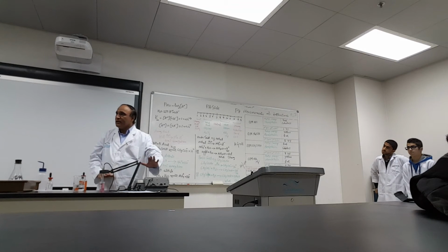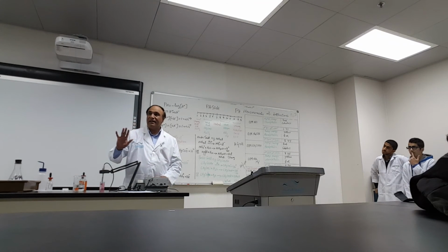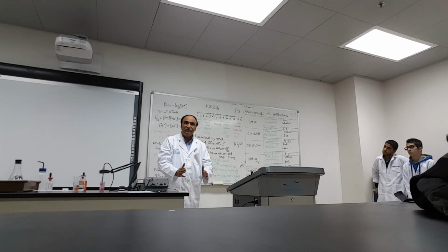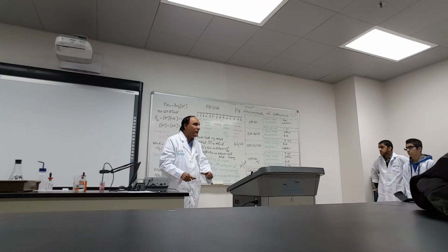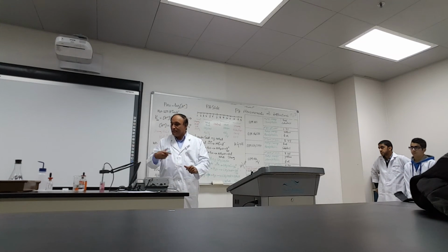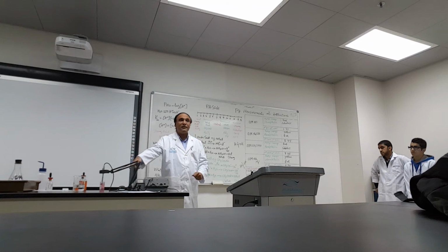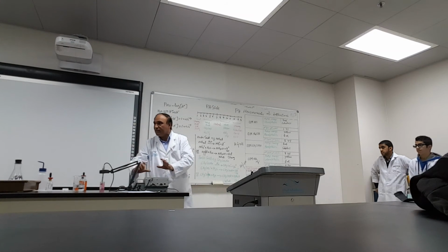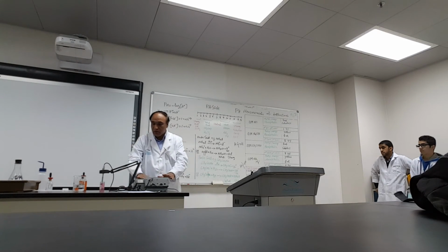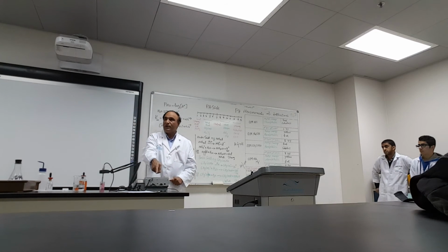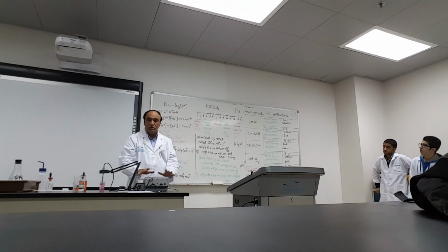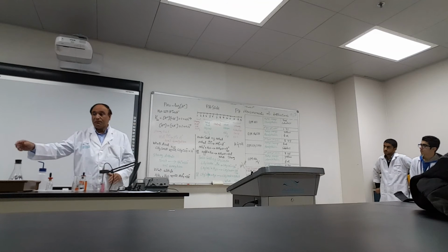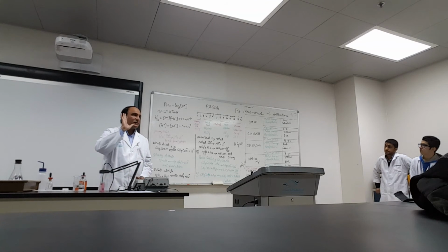So now the meter is ready, like the balance was ready. When it was telling you 9.5, you made it correct. You told the balance, no, not 9.5, it is 10. Similarly, I told the meter what pH I am giving. I told it that it is 4.1. Before you came, I did all the work over there. I told it, look, this is 4.1, and now it is telling me 4.1. It means that now it is ready to use for all these solutions. If I put any solution, it will give me the exact answer.